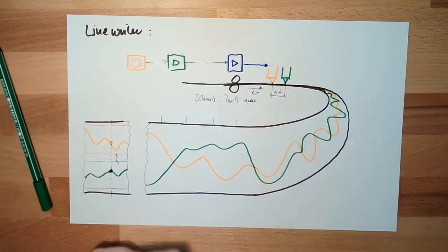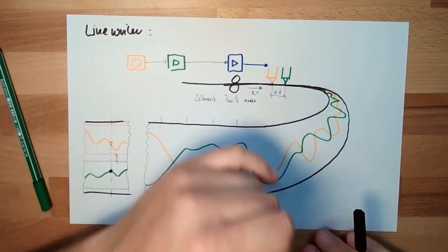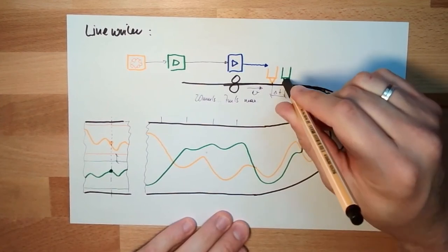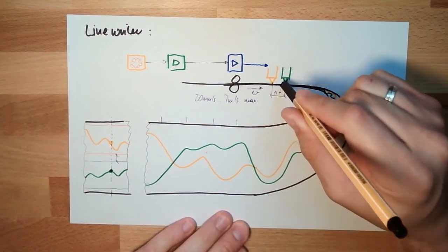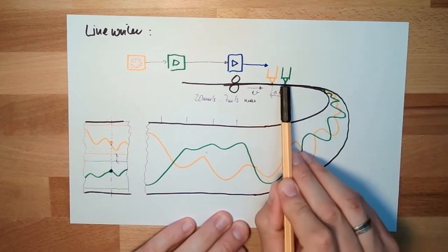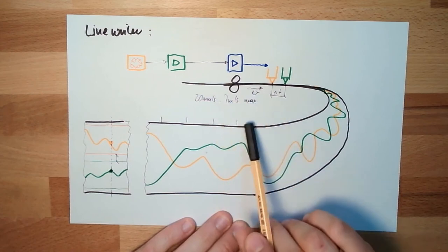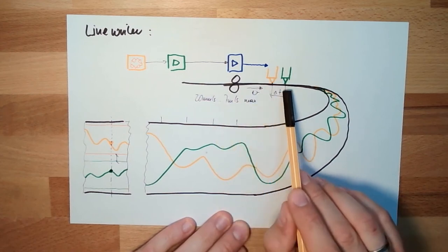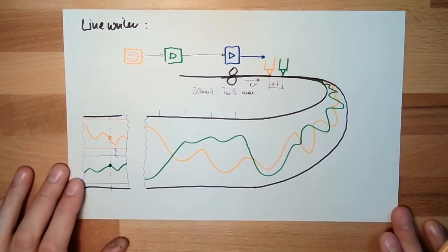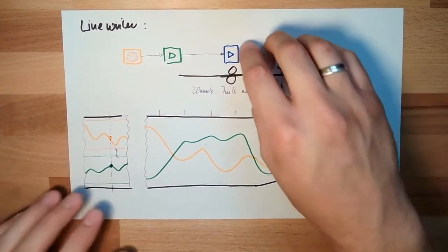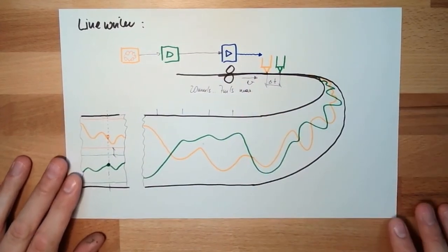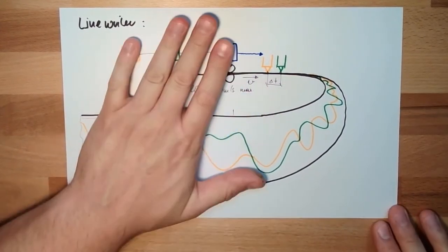And this distance here, because the paper speed means point in time, this means this pen here needs to write what is actually happening a little bit later than this pen. Exactly this time later, a function of the speed. Because it's located later on the paper, it needs to print later, it needs to move later. So there needs to be some kind of buffer buffering the measured information. Okay. That's a line writer.